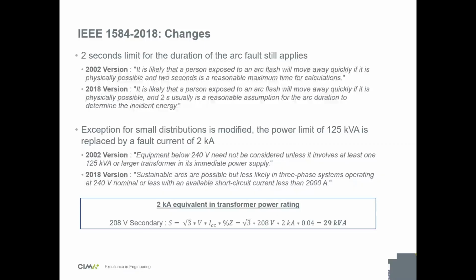So the worker is not subject to the arc flash for, let's say, 1,000 seconds. If the protection takes 1,000 seconds to trip, you don't calculate the energy for 1,000 seconds because it's unbelievably high, and the worker will have time within that period to move away. So there was a 2-second limit. It doesn't apply in bucket trucks, for example, or areas with restricted space. It's been maintained, so the 2-second limit is still there, but you have to be careful that it only applies when you have enough space to move away. If it's in a bucket truck, it doesn't apply.